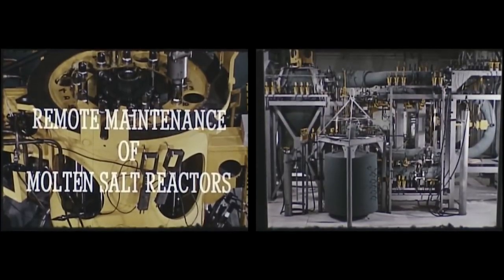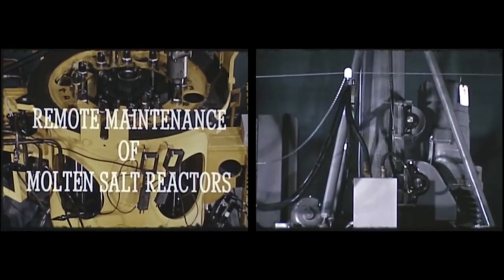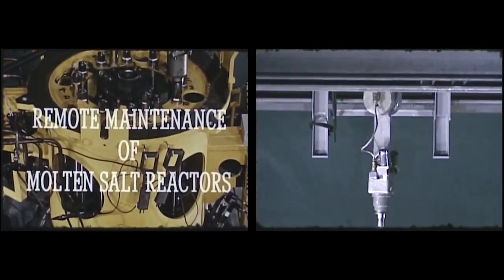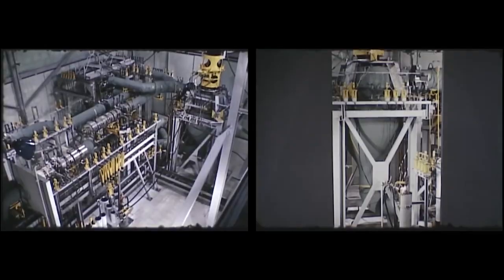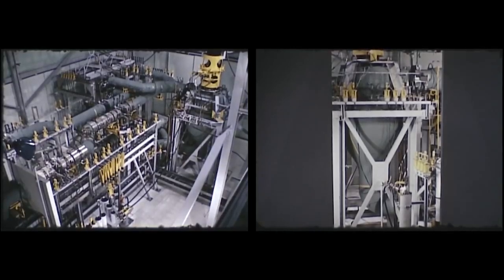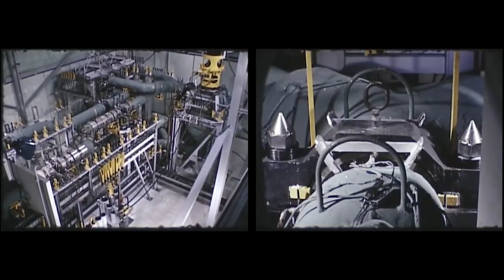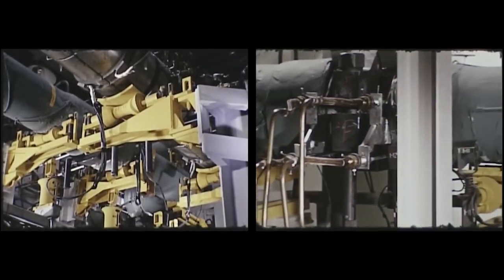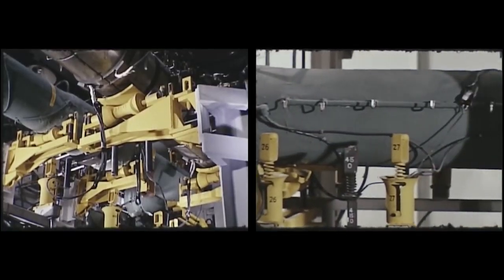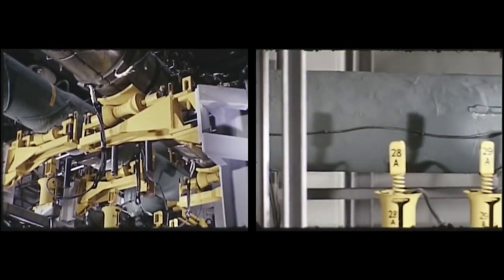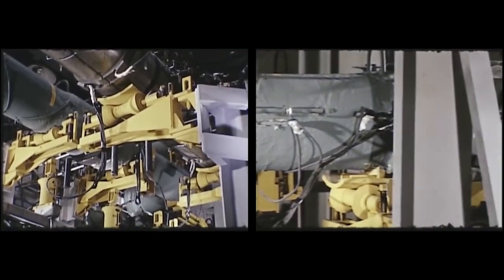The laboratory initiated a program to develop component maintenance and replacement through remotely controlled operations. A mock-up of a small reactor system, 20 thermal megawatts in size. The reactor is connected to the primary piping circuit by two 6-inch mechanical joints of the freeze flange type. Specially designed adjustable spring supports permit all piping to expand or contract freely without overstressing the pipe.